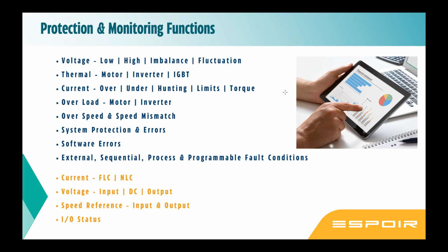Overload, motor overload or inverter overload. Certain parameters it will sense, and then it trips on a condition-based tripping on overload. Now, how does the drive trip? It purely measures the current. All the trips are purely based on current sensing.